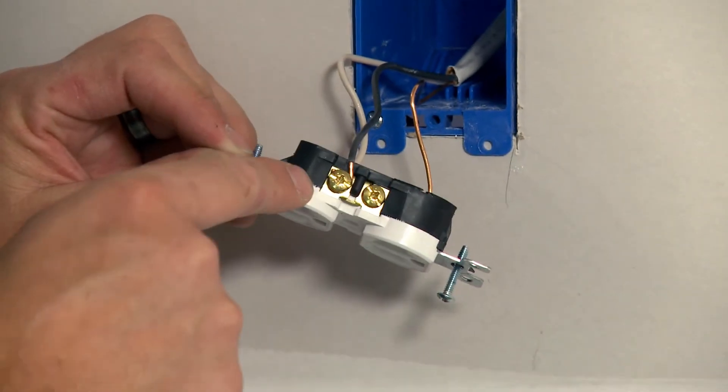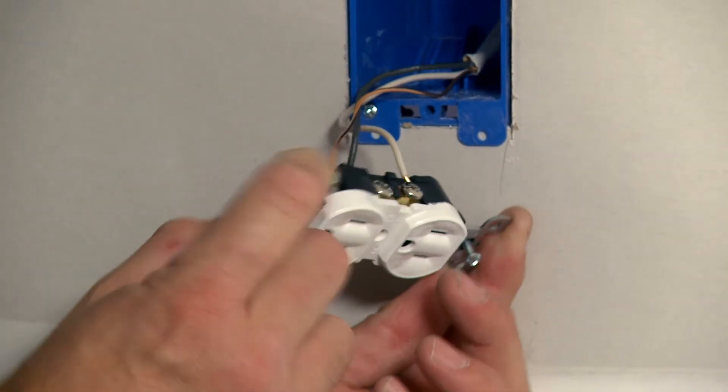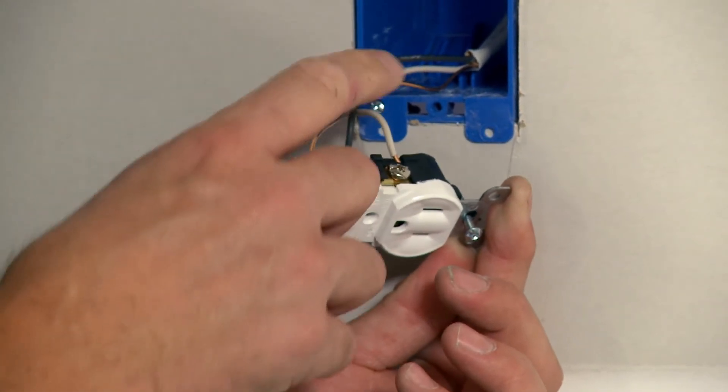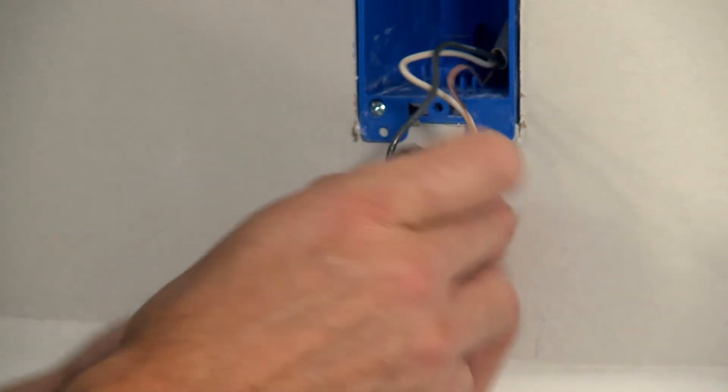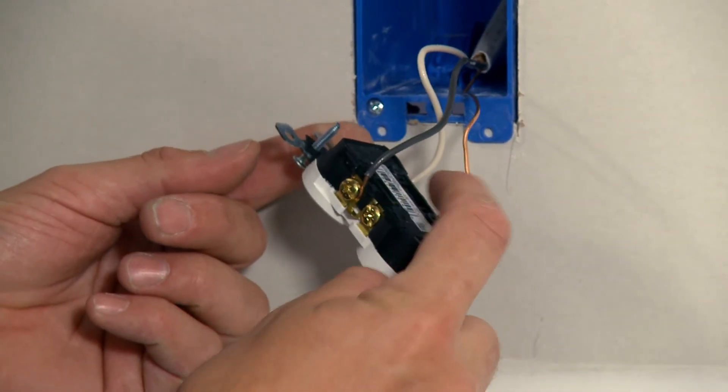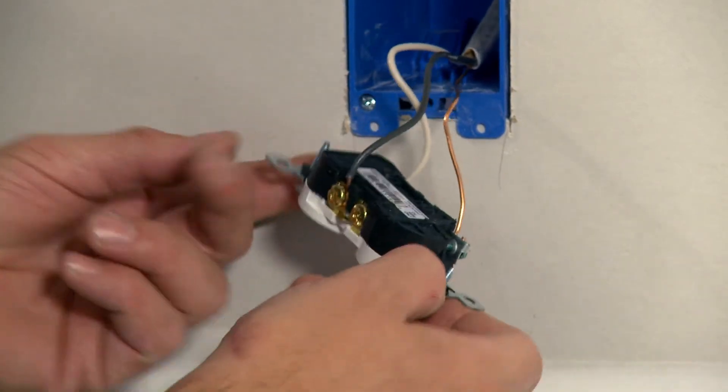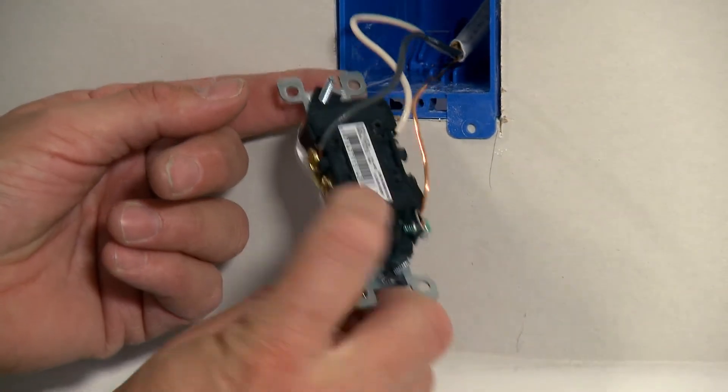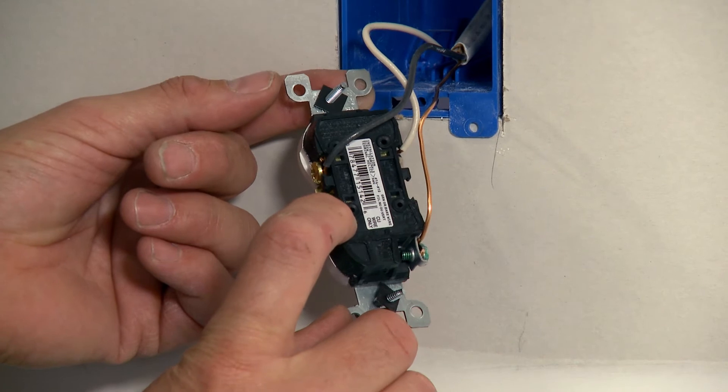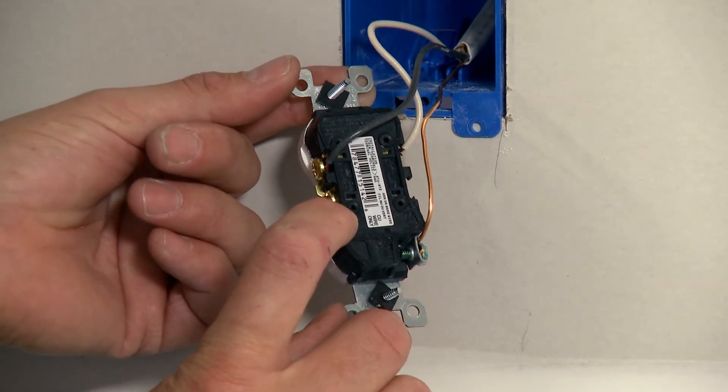We've got our hot coming in on the gold. We've got our ground over here. It's green in color. We've got the neutral coming to the white. The back of the outlets are also labeled white and black or white and hot, sometimes neutral and hot, but they're all labeled. You can see, hopefully, these small holes. Can you guys see those by my finger?